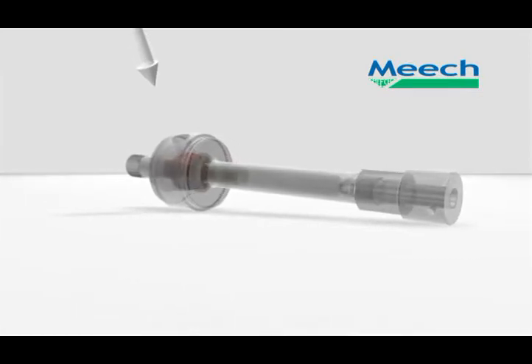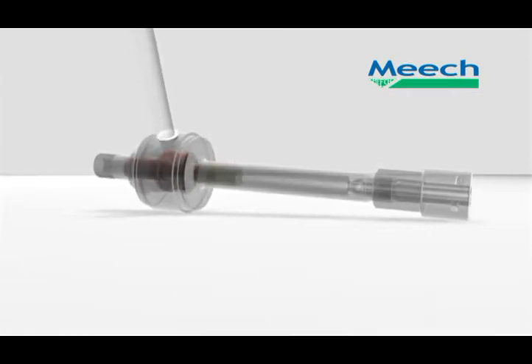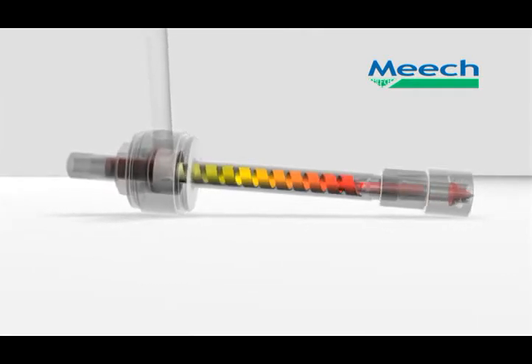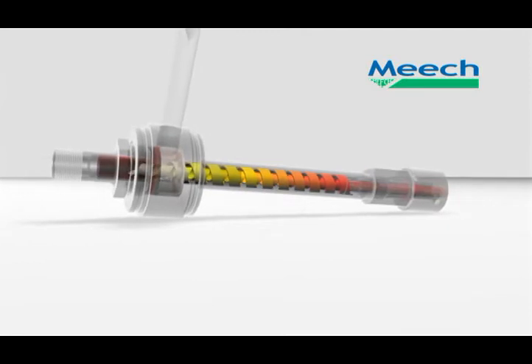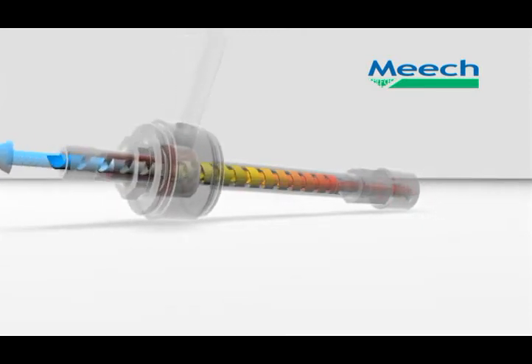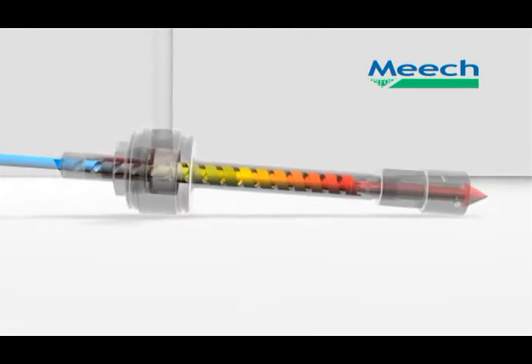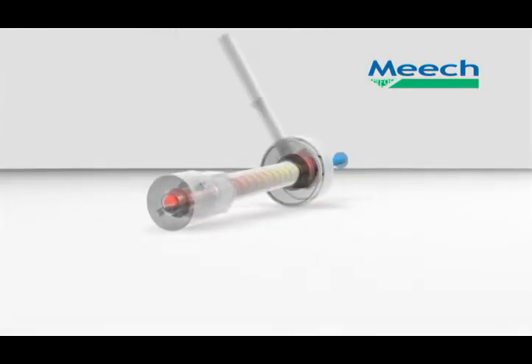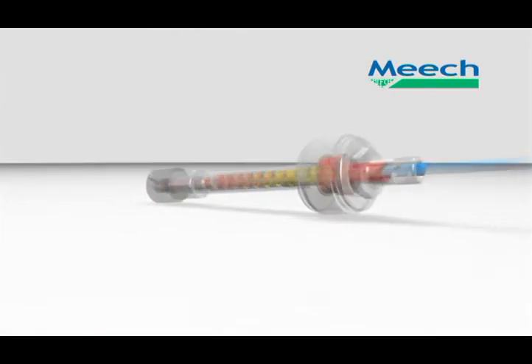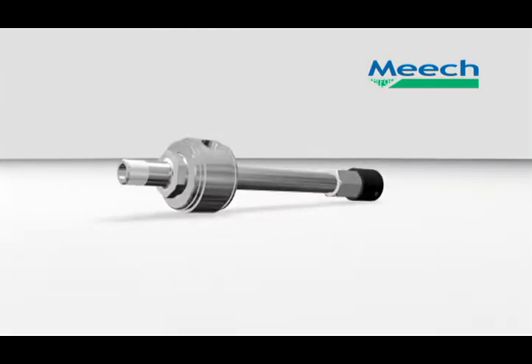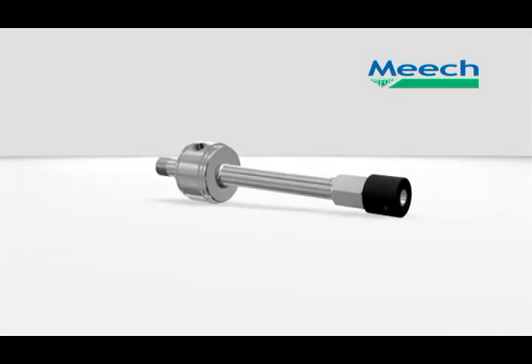So, how do they work? As the animation shows, compressed air enters the spin chamber. This causes the column of air inside the tube to rotate at speeds up to 1 million RPM. The air at the outside of the column, moving very fast, has a lot of energy and is hot. The air at the centre of the column, moving relatively slowly, has little energy and is cold. The hot outer air is bled off at one end of the tube and the cold inner air at the other. The percentage of the air exiting the cold end is called the cold fraction and is adjustable by a control valve. The cold fraction can be controlled and adjusted in 2 ways.